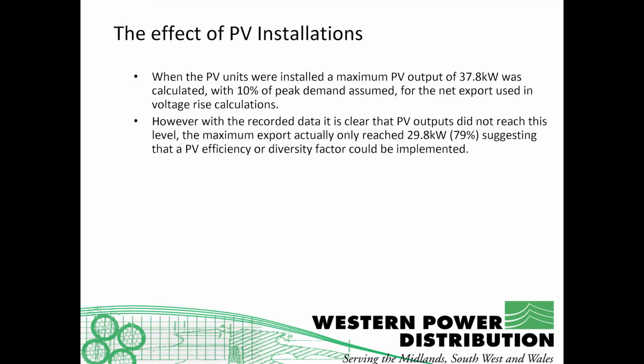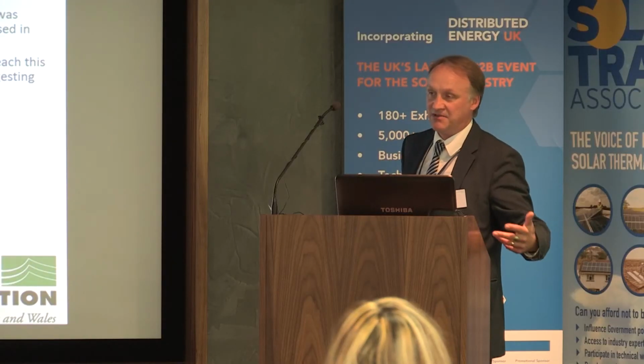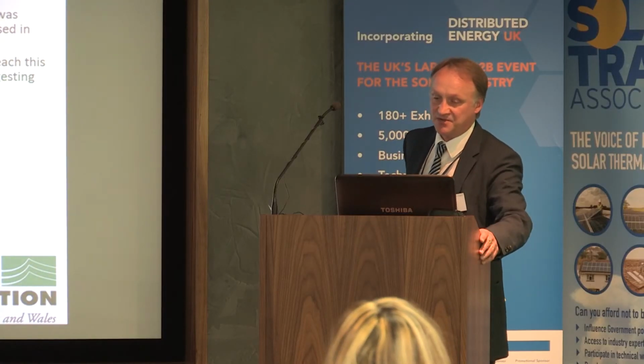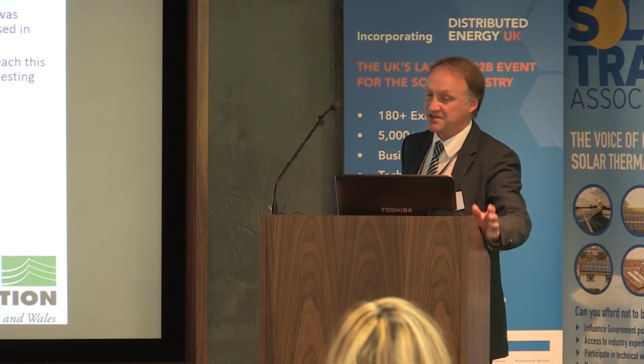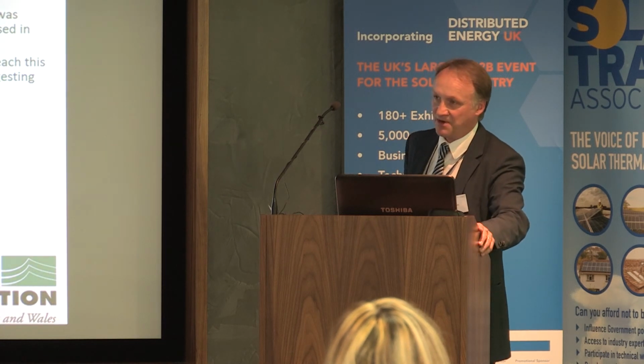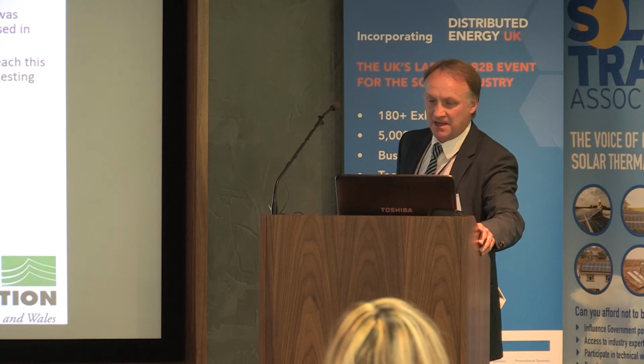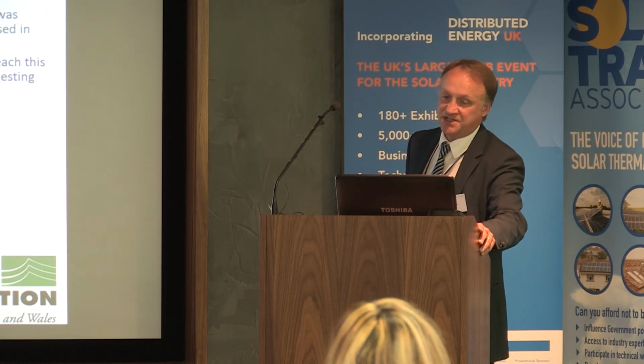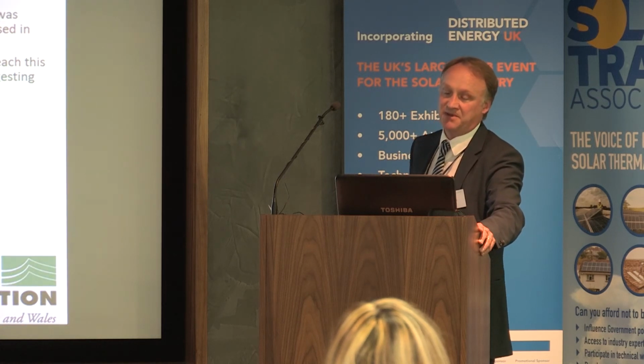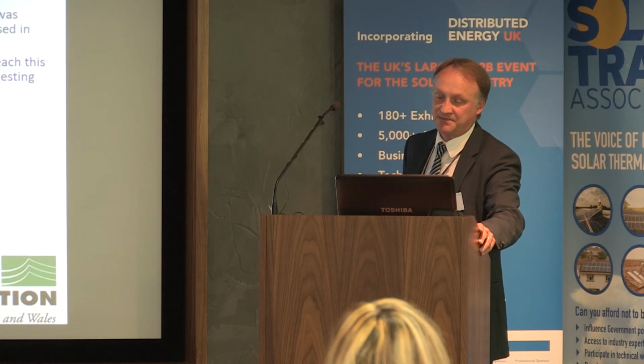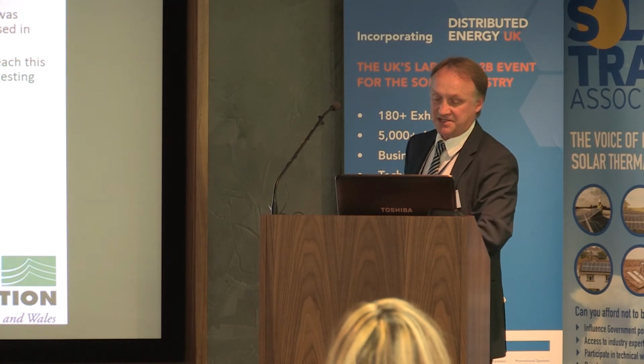However, with the recorded data, it's clear that PV outputs did not reach this level. The maximum export actually only reached 29.8 kilowatts, which is 79%. For the LV templates we were looking at 81% of the installed capacity, and this one has come out at 79%, so the two are in the same ballpark. That suggests that maybe a PV efficiency or diversity factor could be implemented when we're looking at domestic PV installations.